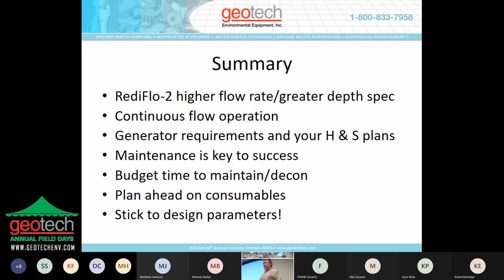Maintenance is the key to success. These small components, O-rings, Teflon parts, are easy to carry around. When I was doing field work, we had a little tackle box. We had Teflon parts, we had motor pins, we had O-rings, we had whatever we needed, and kept it in the box with the VFD. If you go to remote places like Idaho or Montana, which I did a lot of work in, next day air is like 4:30 the second day. So you can lose a lot of time. That's a lot of per diem. That's a lot of sitting around. Plan ahead on consumables, tubing, other components that you may need to manage the project, and stick to the design parameters. Don't use these pumps for anything other than purging and sampling. And you'll have a much better experience.